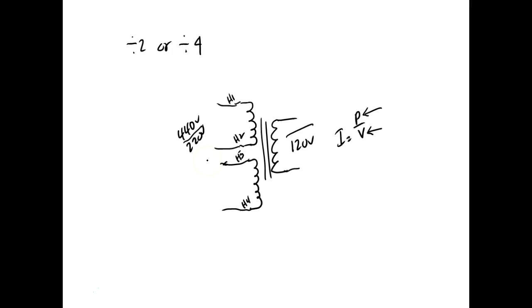So how would we wire it for high voltage? Let's say I'm going to put 440. What we want to do is use the turns ratio, which they'll give you. So we can wire this as 2-to-1, or we can wire it as 4-to-1. On the 2-to-1, every 2 turns of the primary gives 1 turn on the secondary. For the 4-to-1, every 4 turns of the primary gives 1 turn of the secondary.